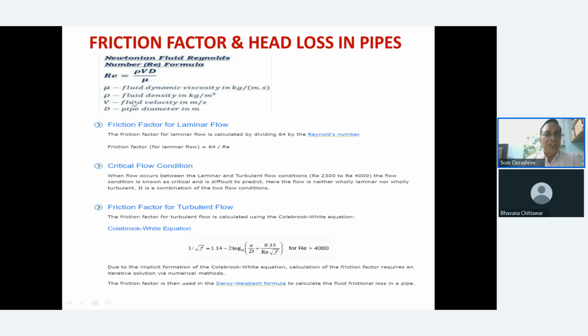Its velocity is in meters per second, and the pipe diameter in meters is D. So you calculate a Reynolds number. From the Reynolds number, if it is a laminar flow, that is, less than 3000, you can use this as the friction factor for laminar flow. And if it is a more turbulent flow, then use the Colebrook-White equation to find out the friction factor F.